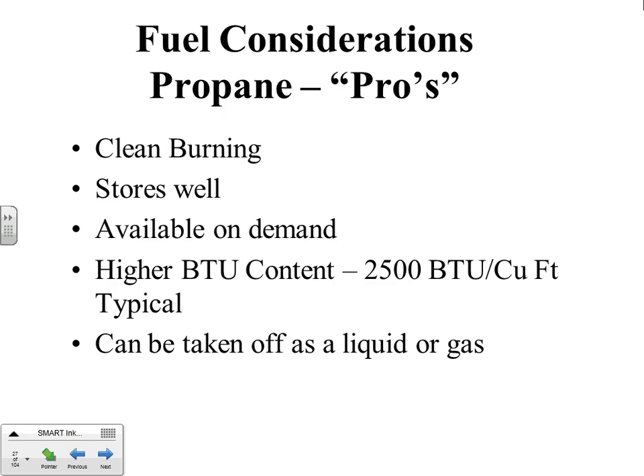Propane. And basically the propane is the same basic carburetor as the natural gas. It's set up a little differently, and because it's a higher BTU fuel, it's adjusted a little differently. But on the pro side for propane, it's very clean burning, stores well. It's available on demand from your fuel supplier. It does, like I said, it's got a higher BTU content. It's 2.5 times more energy than the natural gas system. And it can be taken off as a liquid or a gas. And I'll get to that in a minute.